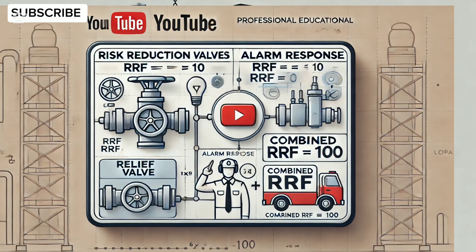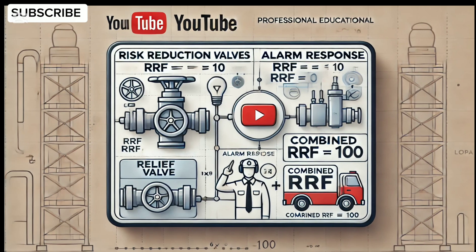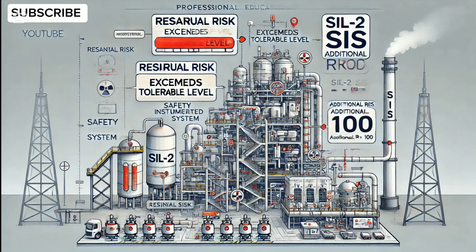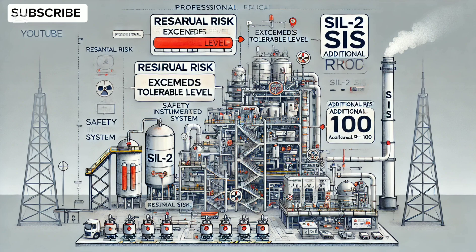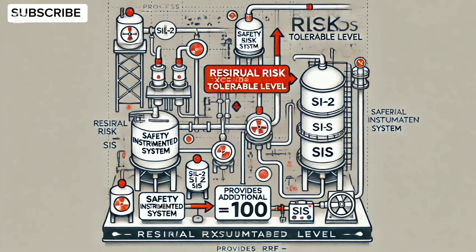The relief valve has a risk reduction factor (RRF) of 10, alarm response has an RRF of 10, giving a combined RRF of 100. The residual risk, however, still exceeds the tolerable level. Therefore, a SIL-2 safety instrumented system (SIS) is recommended, providing an additional RRF of 100 to meet safety standards.